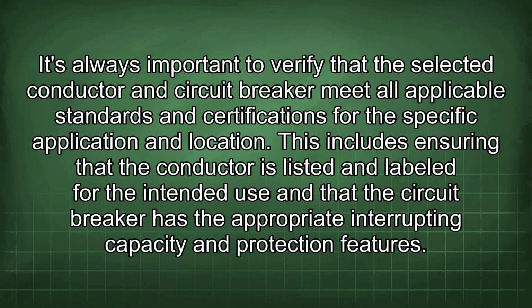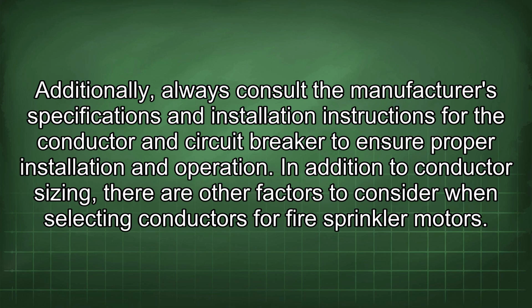It's always important to verify that the selected conductor and circuit breaker meet all applicable standards and certifications for the specific application and location. This includes ensuring that the conductor is listed and labeled for the intended use and that the circuit breaker has the appropriate interrupting capacity and protection features. Additionally, always consult the manufacturer's specifications and installation instructions for the conductor and circuit breaker to ensure proper installation and operation. In addition to conductor sizing, there are other factors to consider when selecting conductors for fire sprinkler motors.